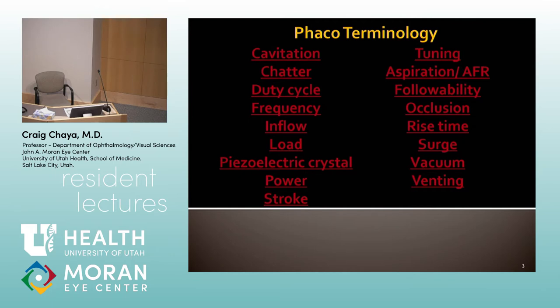Rise time is — once you've occluded your tip into a piece of cataract — the rate at which vacuum builds. Occlusion as a setting means power surges when you've achieved occlusion. And then surge occurs when you lose that occlusion. You sort of lose that tension, and all of a sudden you get a surge — which is a very dangerous part of that.